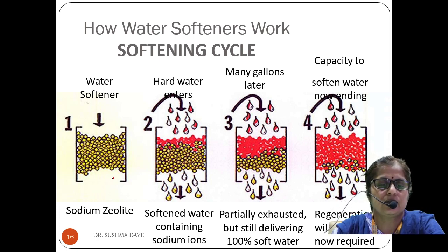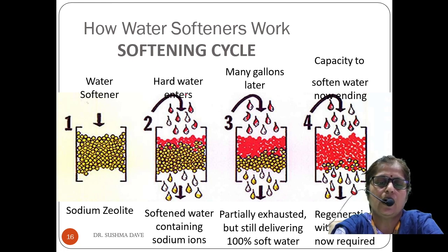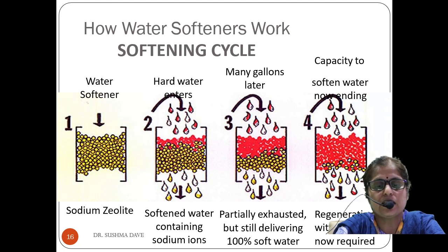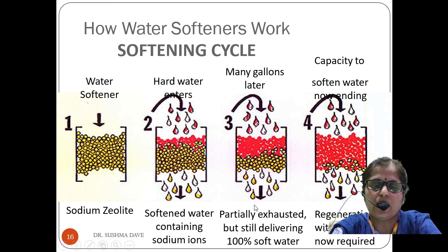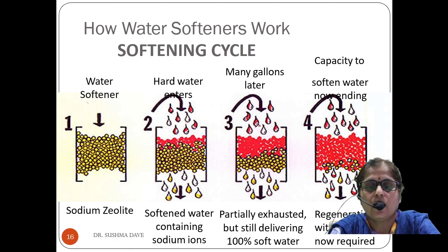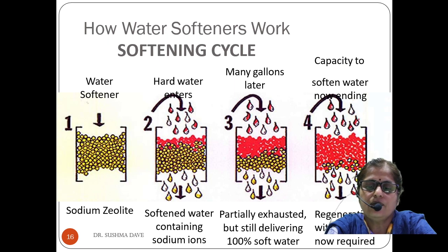The yellow-colored granules represent sodium zeolite. When hard water enters, it contains red-colored particles representing calcium and magnesium ions. Once these move towards the zeolite, replacement takes place and sodium ions are displaced by calcium or magnesium ions. As many gallons of water are passed through the zeolite bed, it becomes slowly exhausted. At the partially exhausted stage it is still delivering 100% soft water, but when all active sodium sites are completely used up, regeneration is required.